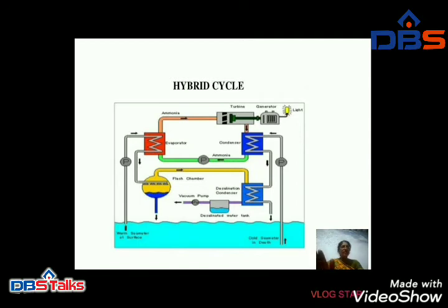In a hybrid OTEC system, warm seawater enters a vacuum chamber where it is flash evaporated into steam, which is similar to the open cycle evaporator process. The steam then vaporizes the working fluid of the closed cycle, on the other side, the ammonia vaporizes.